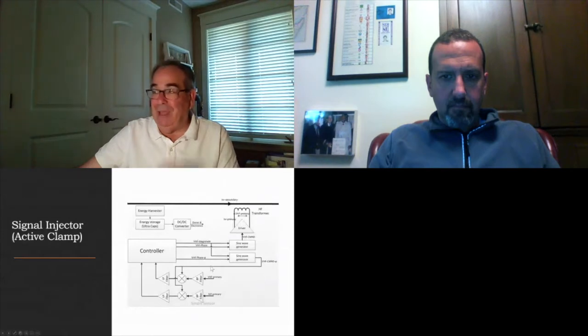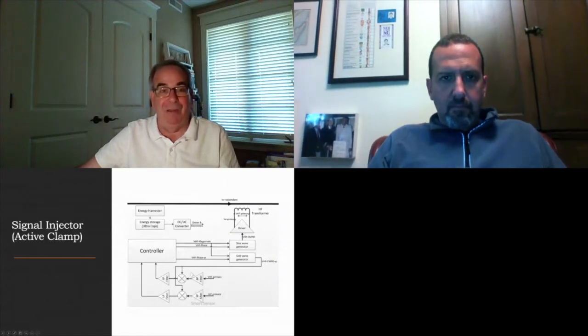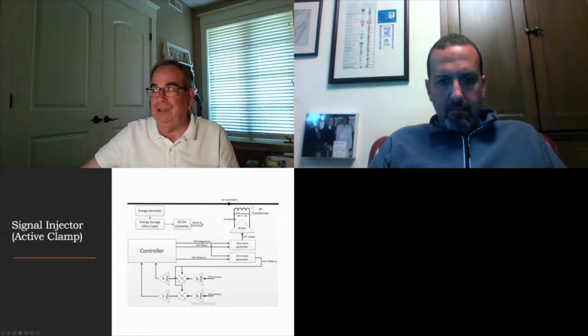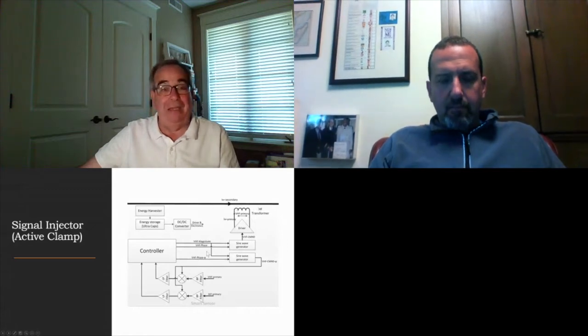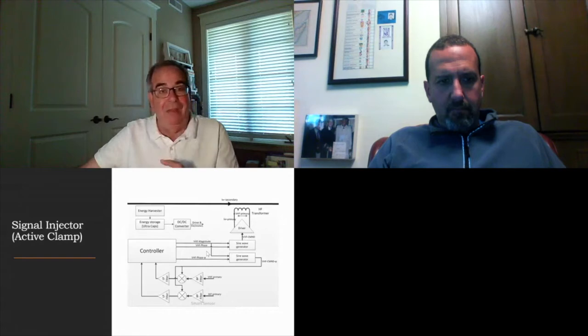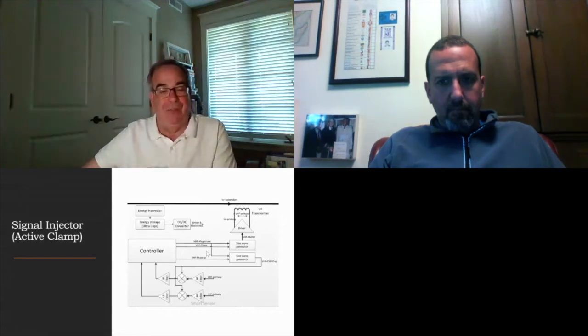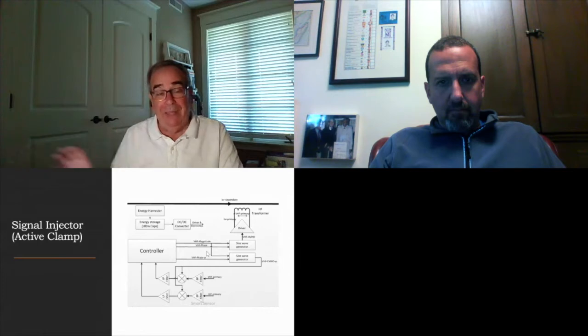Here's the active clamp injecting circuit. It's very simple, really, when you look at it from a block diagram. We're just creating a signal that's induced into the cable itself and controlling that very well, and then measuring the results of that. So we apply a voltage to the circuit, it induces a current into the cable, and we measure that current flow.